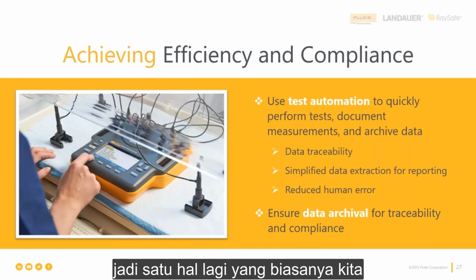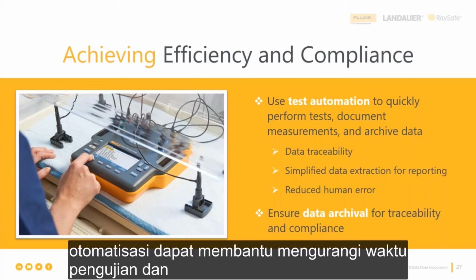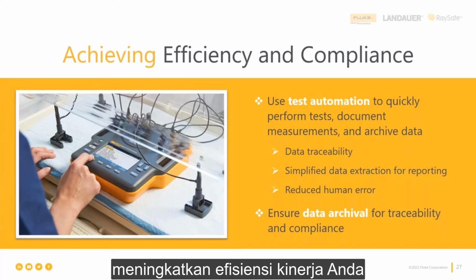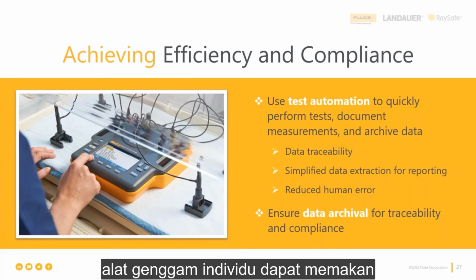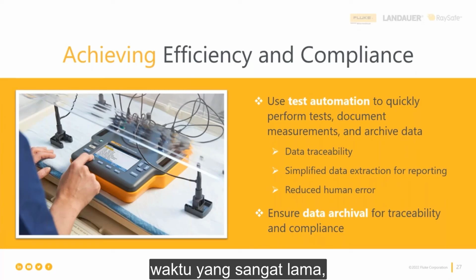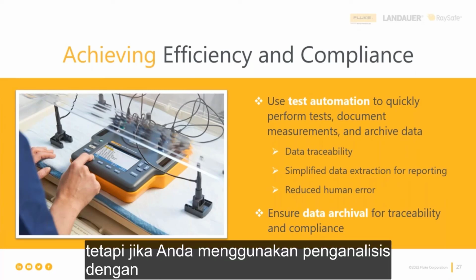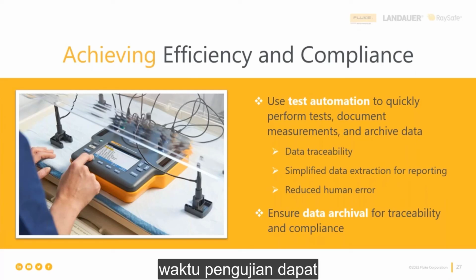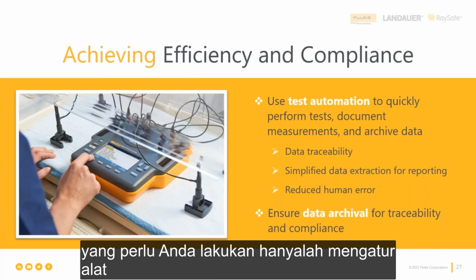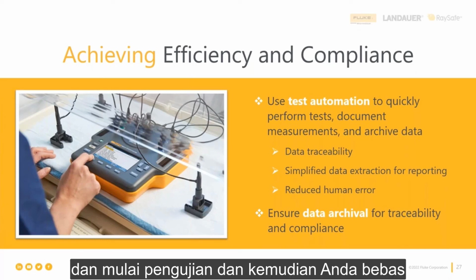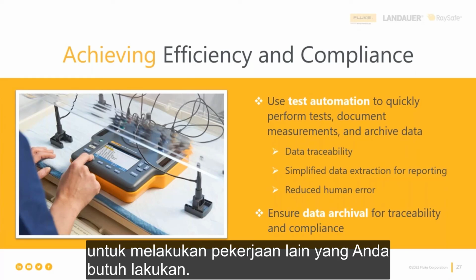So one more thing that we typically recommend, something that contributes to a successful testing process when it comes to infant incubators, is test automation. The reason is that test automation can help reduce test time and increase the efficiency of your performance. Testing each parameter one by one, or using individual handheld tools, can take a very large amount of time. But if you use an analyzer with built-in test automation, that test time can be dramatically reduced. All you need to do is set up the device and start testing, and then you're free to perform other work if you need to.